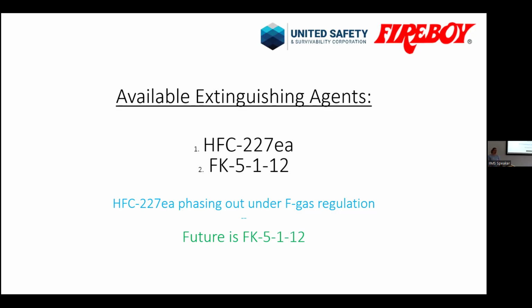So if you want to service, install, or commission fire extinguishers that contain HFC 227, you have to be trained to do that. So you have to have a training certificate. The only authorized body in the UK to do fixed fire extinguishing system training for F-gas at the moment is FIA. So if you come across anyone that does the work or installs and commissions the extinguishers, they should be F-gas trained by FIA for any extinguisher that contains more than 3 kilos of HFC 227. We have to monitor all the suppliers or any engineers that we use, because we are not legally allowed to sell to anyone that's not trained.